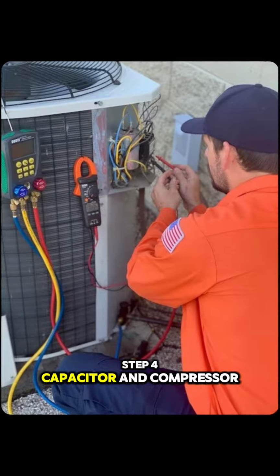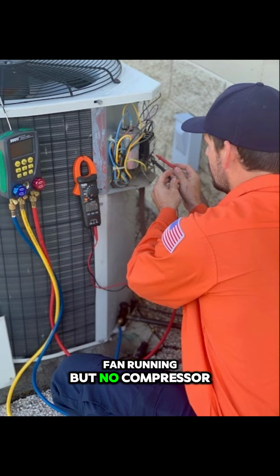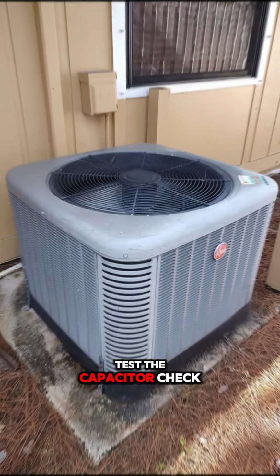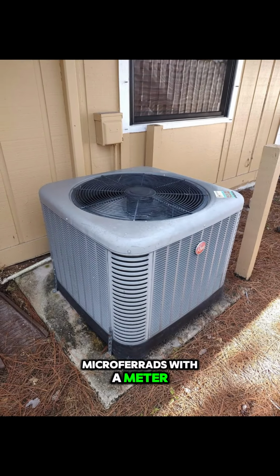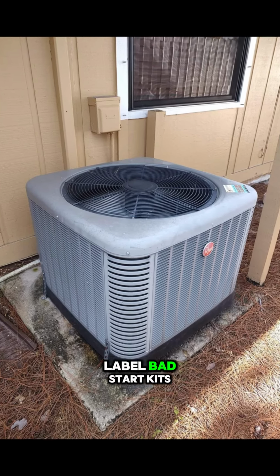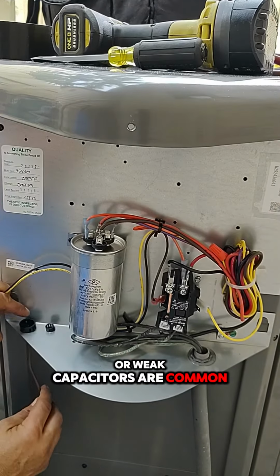Step 4. Capacitor. Condenser fan running, but no compressor? Test the capacitor. Check microfarads with a meter. It must match the label. Bad start kits or weak capacitors are common.